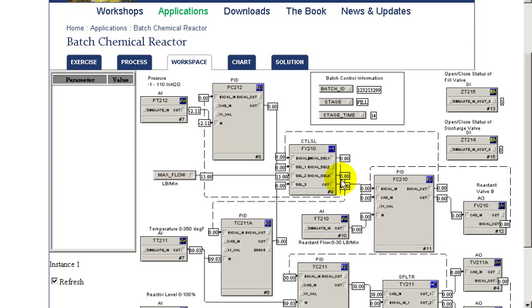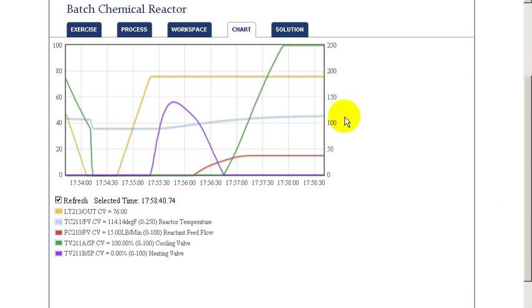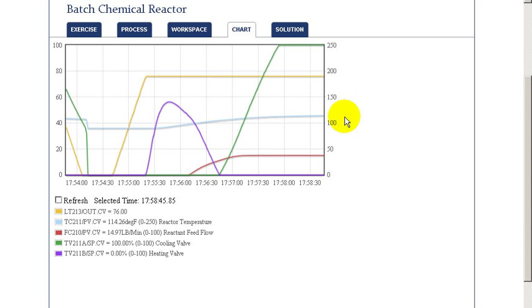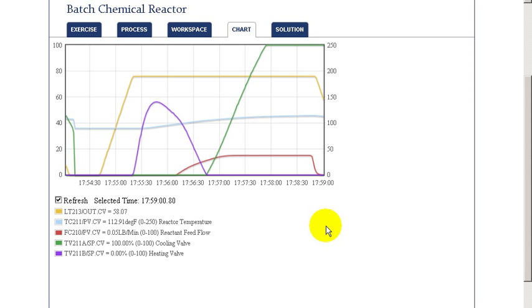With a value of 15, if we look at what happens during the cycle, we become limited during the cycle. But the temperature never rises up to the constraint limit, so we're able to maintain our target during that time frame all the way up to the end of our batch cycle.